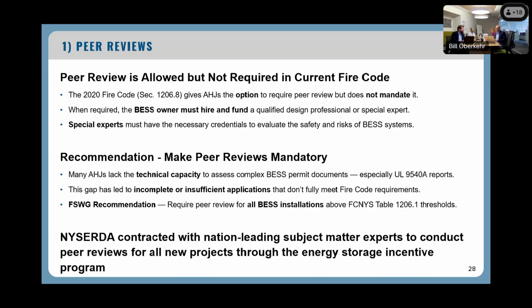But we, in the Fire Safety Working Group, arrived at the opinion that this is an underutilized power. That is why the Fire Safety Working Group's Fire Code recommendations suggested that peer review become mandatory in all cases, so it's no longer a discretionary power for the AHJ to decide. The recommendation is that all systems above 600 kilowatt hours will go through a mandatory peer review, which is also why NYSERDA is stepping in to conduct those peer reviews.